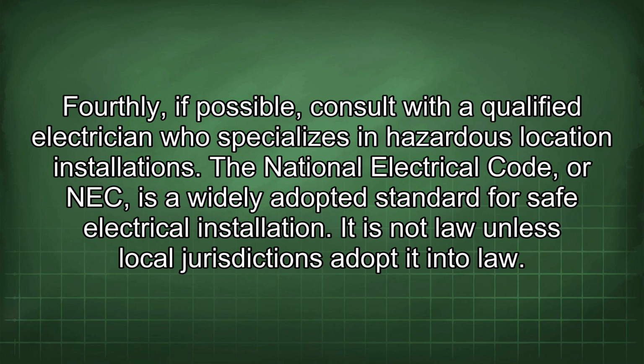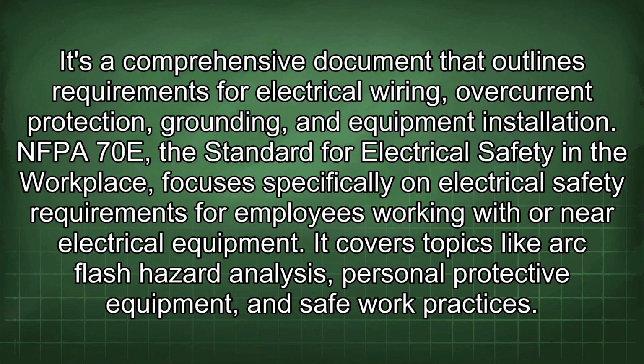The National Electrical Code, or NEC, is a widely adopted standard for safe electrical installation. It is not law unless local jurisdictions adopt it into law. It's a comprehensive document that outlines requirements for electrical wiring, overcurrent protection, grounding, and equipment installation. NFPA 70E, the standard for electrical safety in the workplace, focuses specifically on electrical safety requirements for employees working with or near electrical equipment. It covers topics like arc flash hazard analysis, personal protective equipment, and safe work practices.